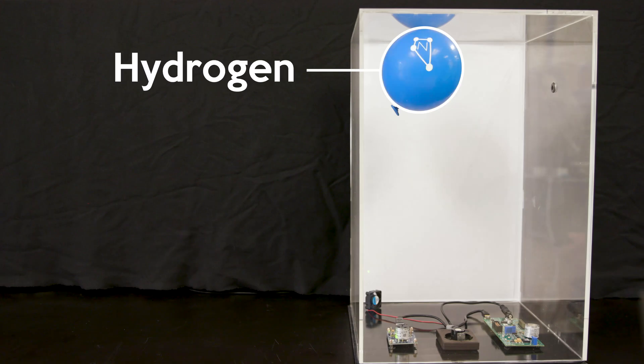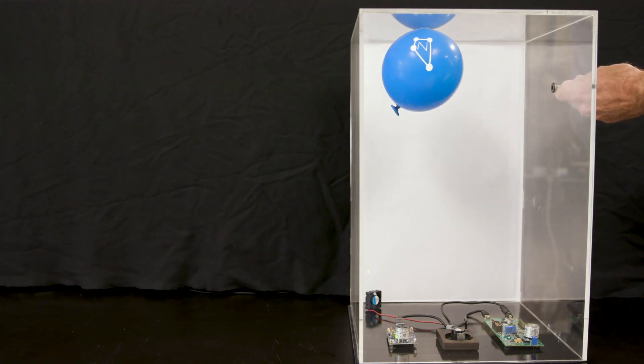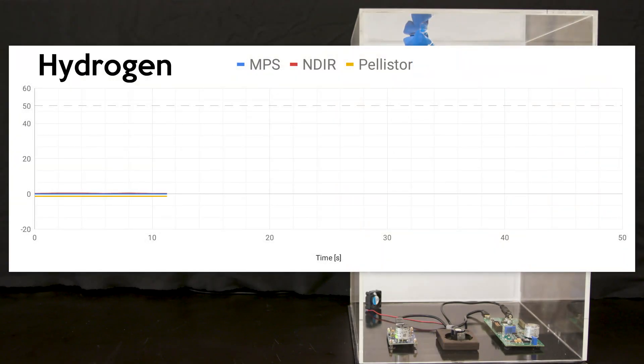Lastly, we have hydrogen. Again, the balloon is filled to the equivalent of 50% LEL for this volume, and I'll pop it. I'll let it circulate a little bit. So the MPS accurately detects hydrogen and reports it at 50% LEL. It also correctly identifies it as hydrogen.